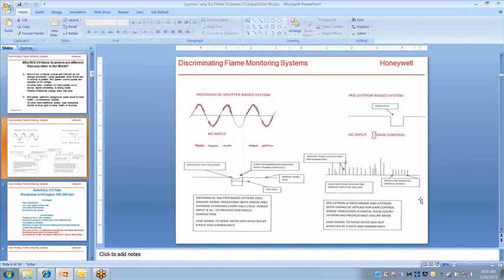This is from the manufacturer. First of all, it's very difficult to simulate a failed tube. Most of the time when the tube fails, they just stop conducting. They go bad. But there are times when contamination inside the UV tube will cause them to produce a signal. By the way, this tube is made by Hamamatsu, so there's no secret. They have tested it and confirmed that's how the tube will behave when it fails in the conduction mode. Okay, thank you.